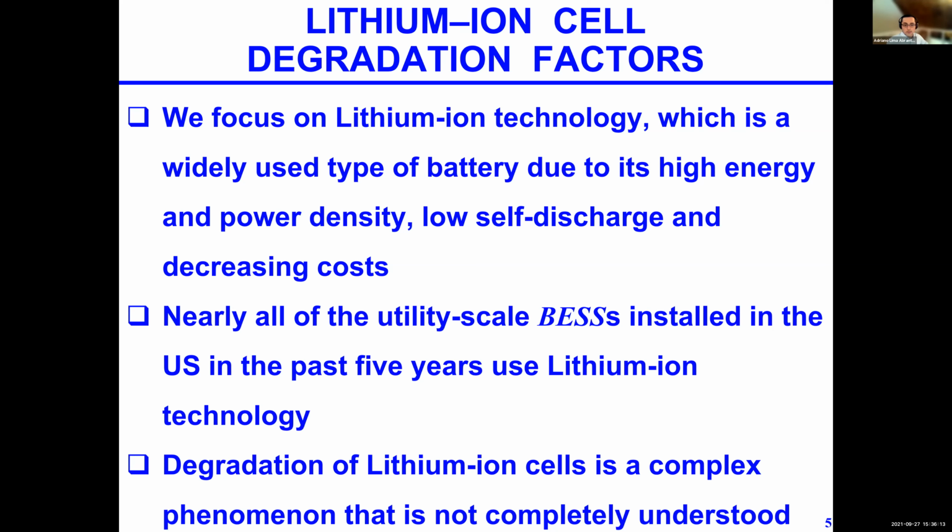And we use a simple model that is based on the depth of discharge. So if you have a battery that's at state of charge 0.5, right? And then you discharge 0.05, and then you charge again 0.05. Then you did a cycle where the depth of discharge was 0.05. And so once you can actually measure how deep the cycles you performed are, you can estimate how much life your battery lost due to performing these cycles.